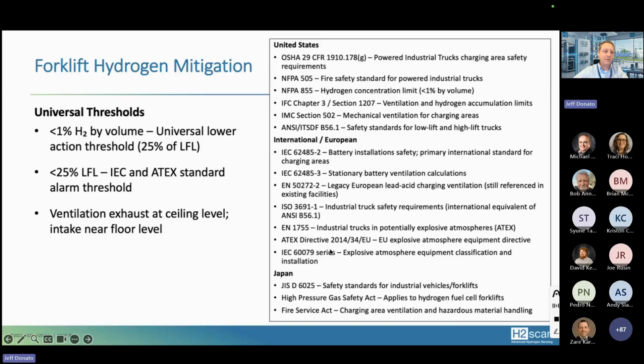It's used in multiple applications to either alarm the customer so they can take manual action, or to activate ventilation systems on site. For a system with a charger charging batteries, such as a forklift or even a substation, they can connect the dry contact relays to the charger system to shut it off if they get a high hydrogen alarm, whether at 1% or 2%, whatever their preference is. There are international standards around controlling hydrogen even in these warehousing locations.